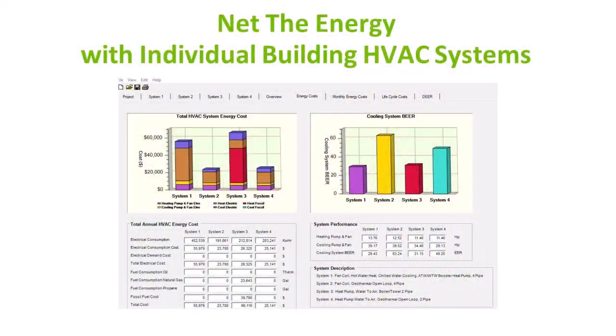That's the building efficiency system tool. I took those 4 systems we just looked at and modeled them in BEST. Upper left is the projected annual energy consumption, and upper right is the system efficiency, the COP of the system, not the equipment. The geothermal components, even though the other two had heat recovery, are going to be more efficient, right?